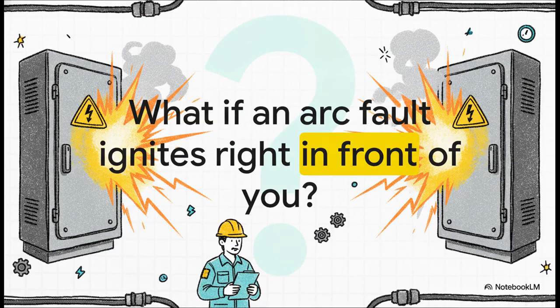Picture this scenario for a second. You're a marine technician. You're standing in a dimly lit engine room corridor right in front of a medium voltage switchboard, humming along at 6.6 kilovolts. And suddenly, an arc fault ignites right behind that closed metal door. What actually happens? We're talking about a contained explosion of superheated, highly conductive gas. This visceral, terrifying reality really sets the stakes for the hardware we're unpacking today, because your life and the safety of the entire vessel literally depends on the design of that cabinet standing in front of you.